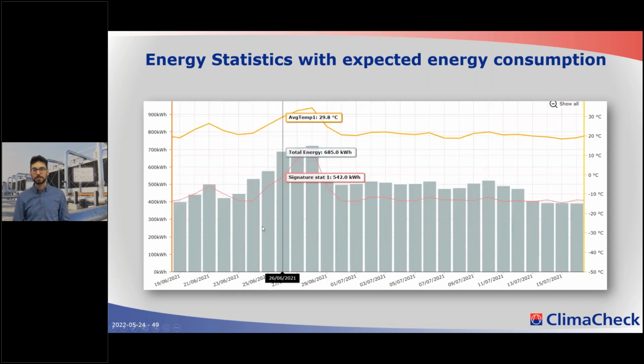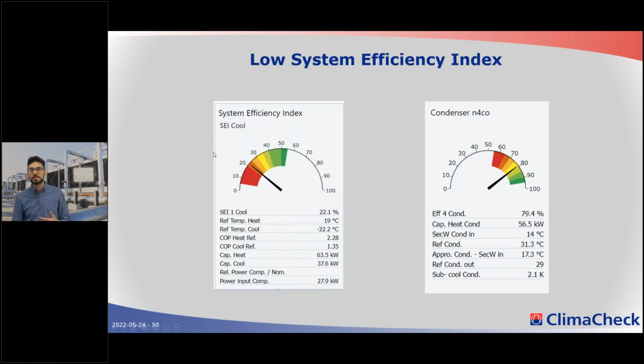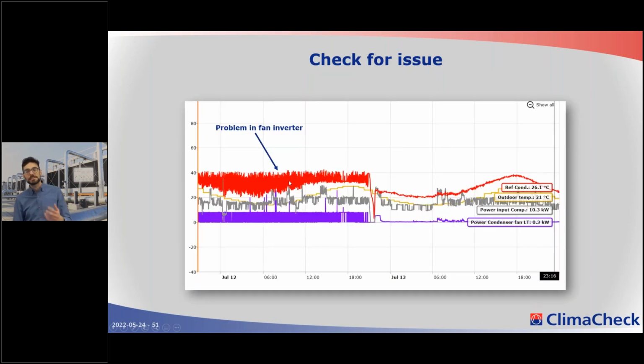Now, let's take a closer look in here. So what we predicted is 540 kilowatt hours, but we're actually using 685 kilowatt hours. This is quite a lot of difference. And at this point, our partner got the alert from our system and wanted to dig deeper into the data to see what is causing this issue. So looking at the system efficiency index, we're seeing that the overall system is performing terribly. And the reason for that is the condenser. Now we've got issues in the condenser. We take a look at that. And in this case, the problem was the fan inverters. They were not behaving as they were programmed to be.